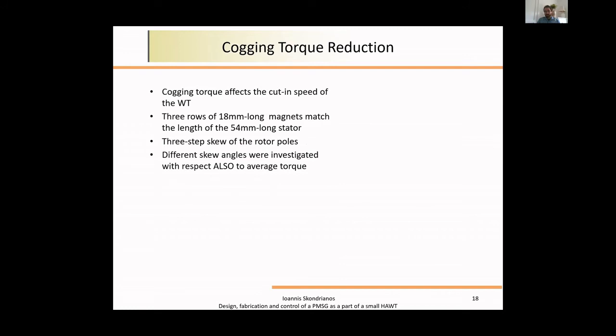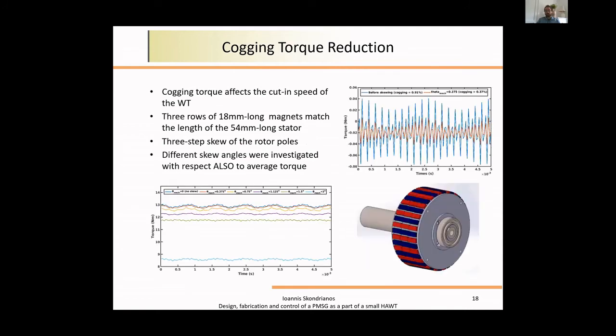Last thing in terms of this model is cogging torque reduction. I already told you how important it was for us. To fight that, we decided to test different skew angles. You can see the rotor consists of three rows of 18 millimeter long magnets, matching the total length of the 54 millimeter long stator. We decided to do a three-step skew of these poles, starting with zero angle up to three mechanical degrees. As the skew angle increased, we could see torque was dropping. However, the best results were given by a skew angle of 0.375 mechanical degrees. It reduced cogging torque from 0.91% to 0.37%, a huge improvement for us.